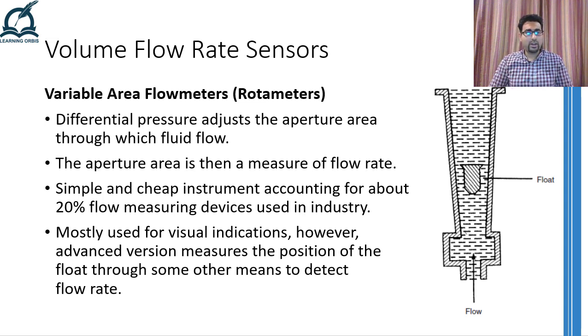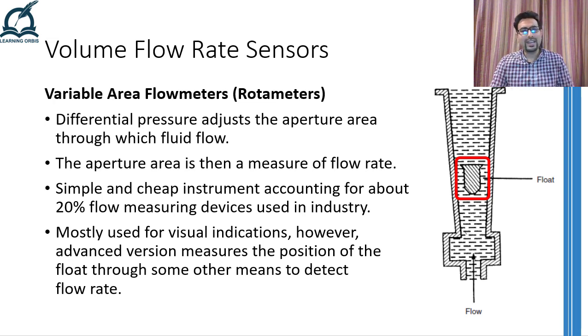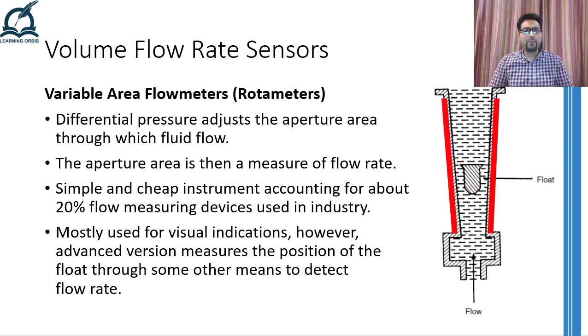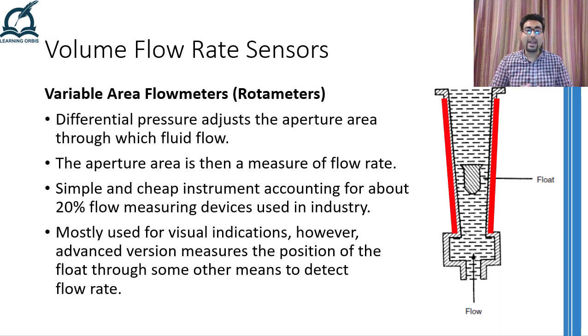Depending on the flow of the fluid and the pressure differential created on both sides of the float shown here, the float will be lifted. When there is no flow, the float will settle down, hence blocking the path of the fluid completely. Depending on the volume flow rate, the float will rise up and settle at a point where the pressure created by the fluid on one side equals the pressure head on the other side. The conical shape of the pipe allows higher pressure to develop on the top of the float as it rises, and hence a point will come when the pressure at the top balances the pressure at the bottom.